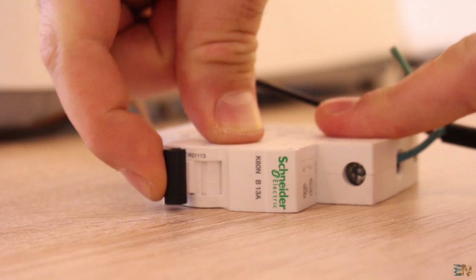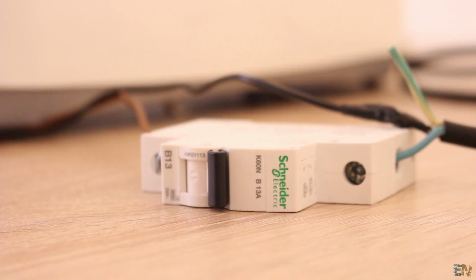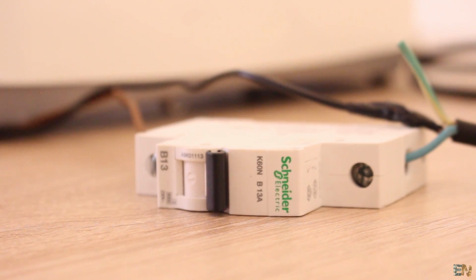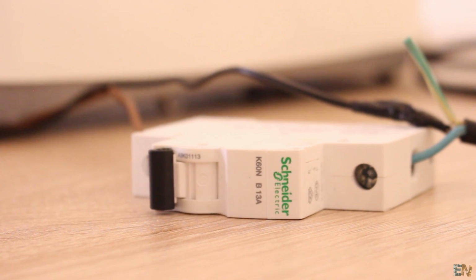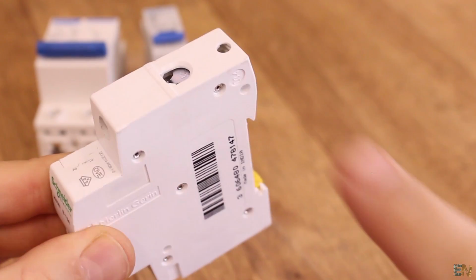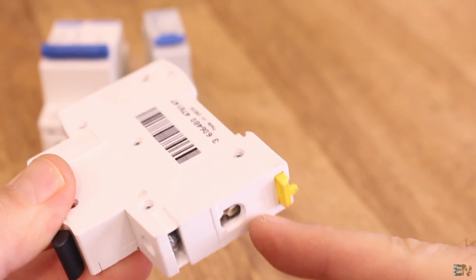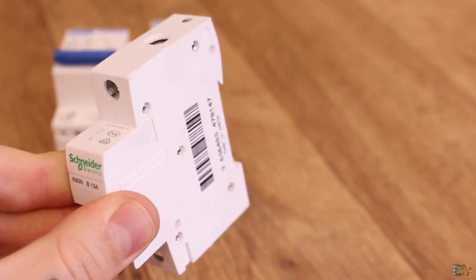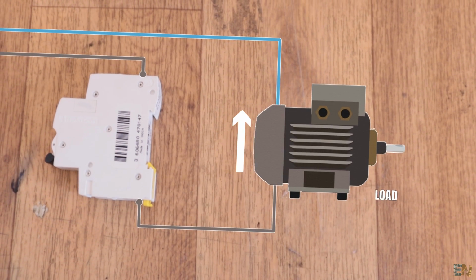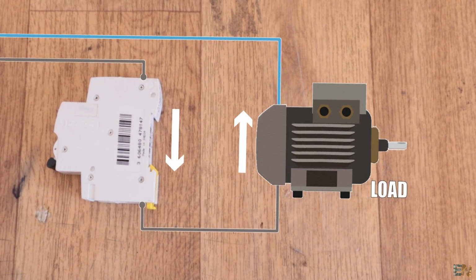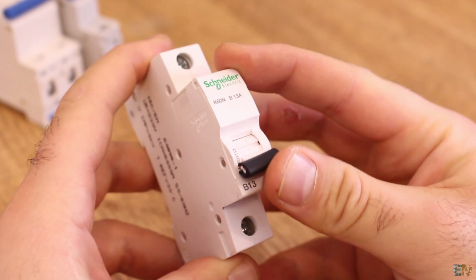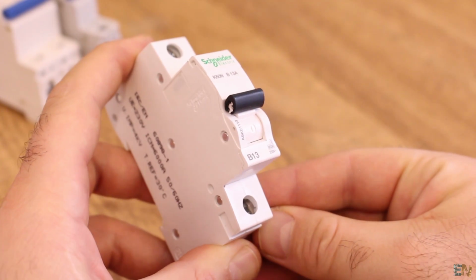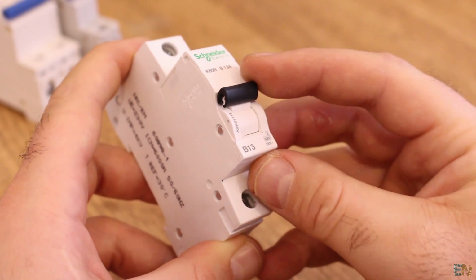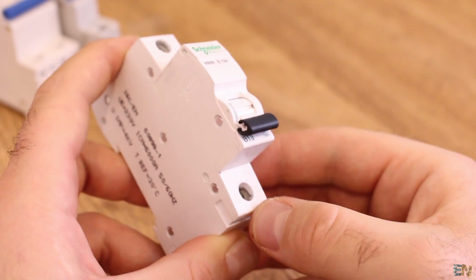Okay, so by that it opens the circuit and we save the wiring from a fire or melted wires. But now let's open the MCB. So power is connected in series to this device from here to here. So the same amount of current passing through the load will pass through the breaker as well. When the switch is up, the circuit is closed, so current is flowing. When the switch jumps, it opens the circuit, but let's see how.